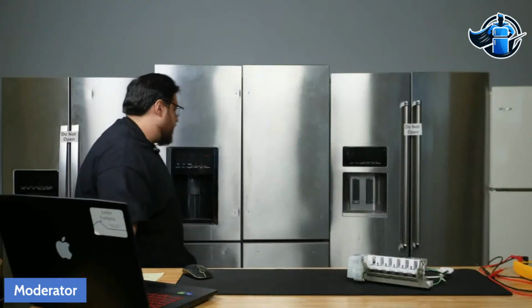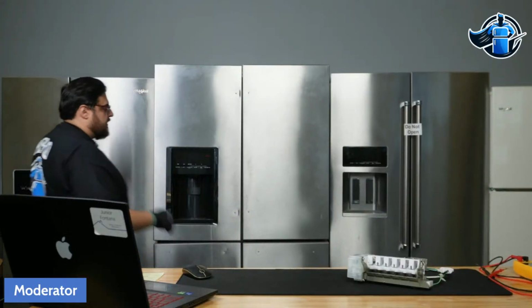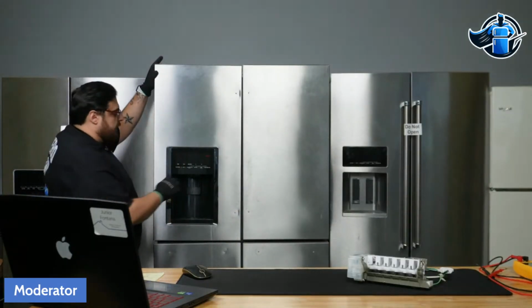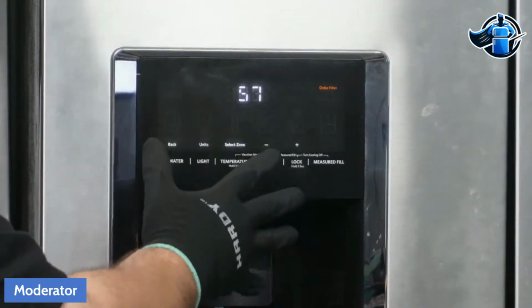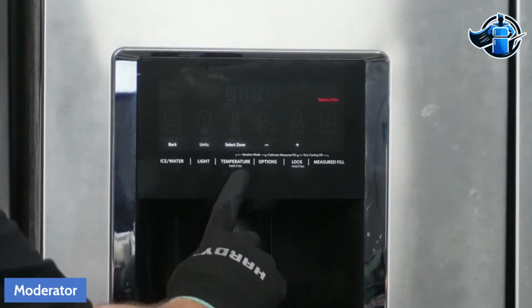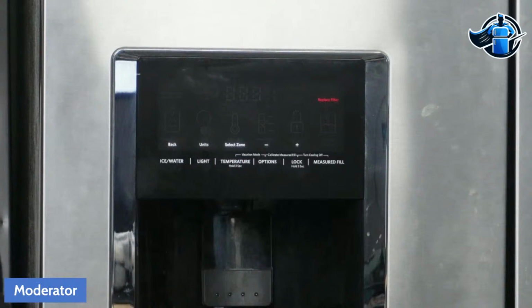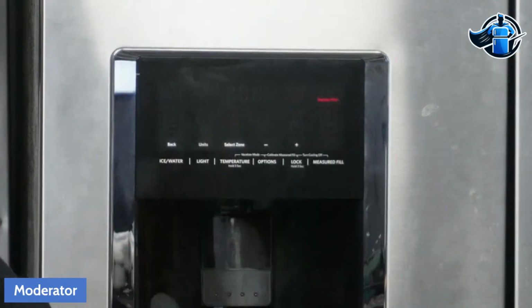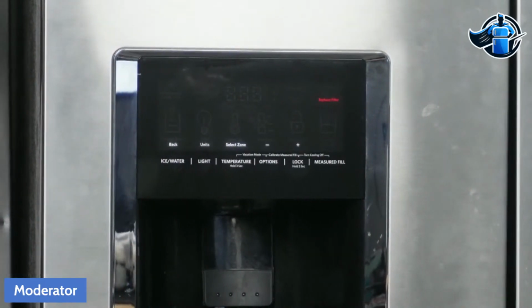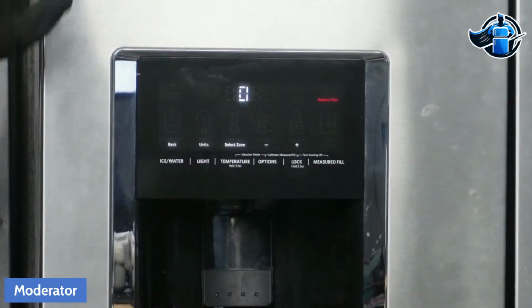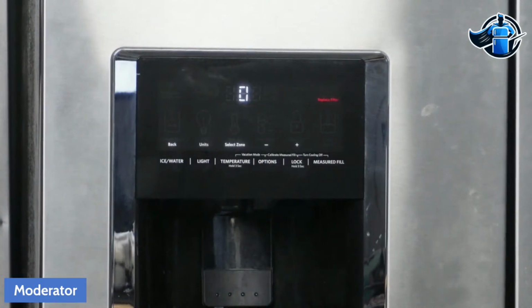All right, now let's get back over here to diagnostics, and then we go down to test 57. To activate this test, you will press the third button, which will then start the harvest cycle for the unit, and the ice maker should operate. We'll talk about the codes for that in a moment.